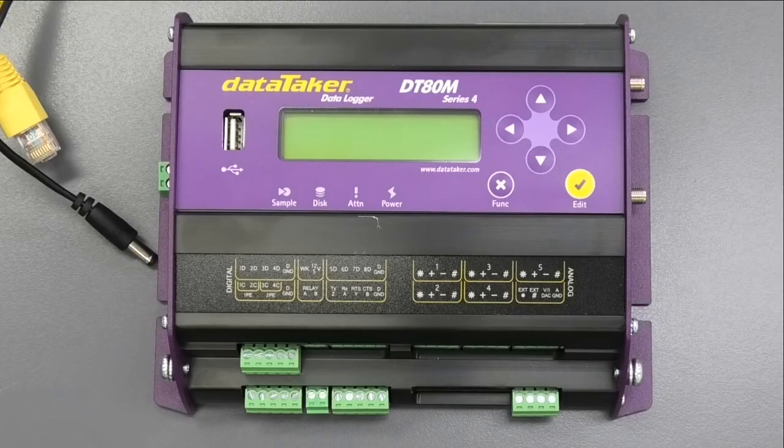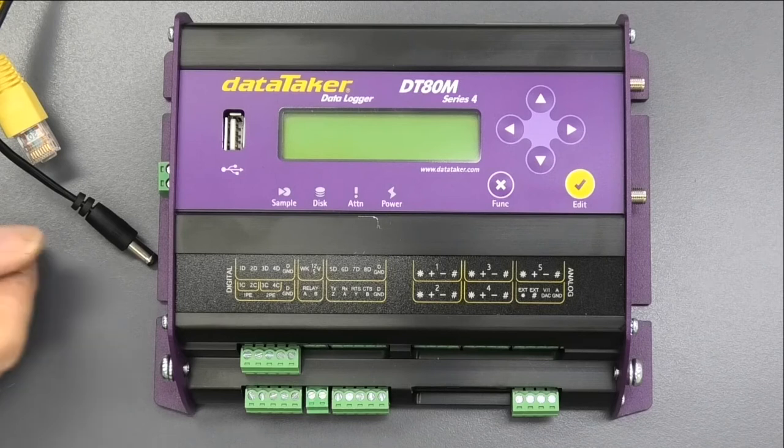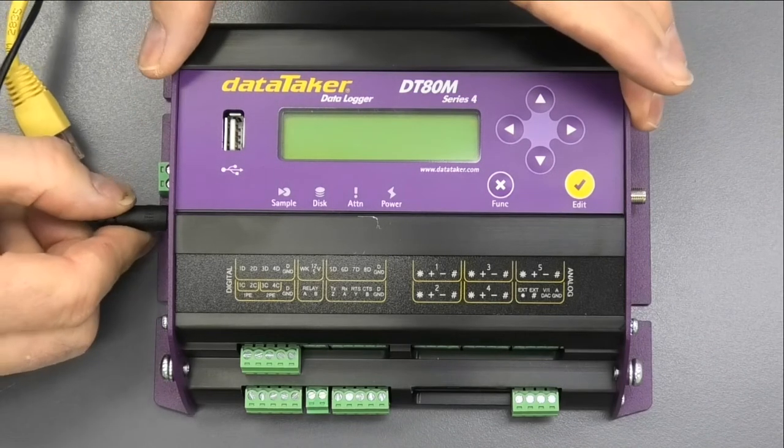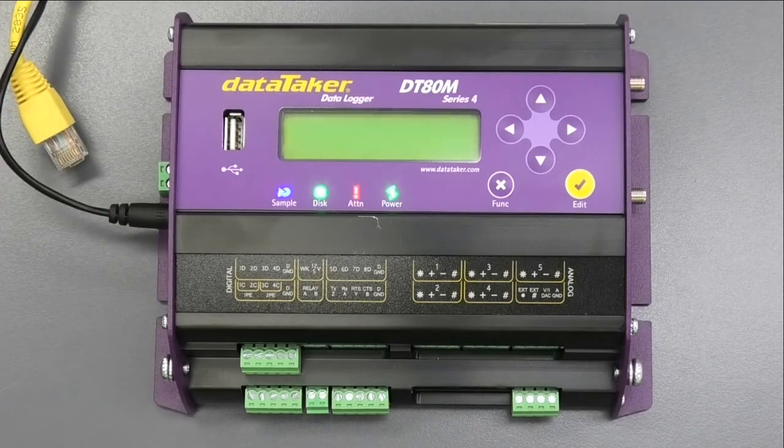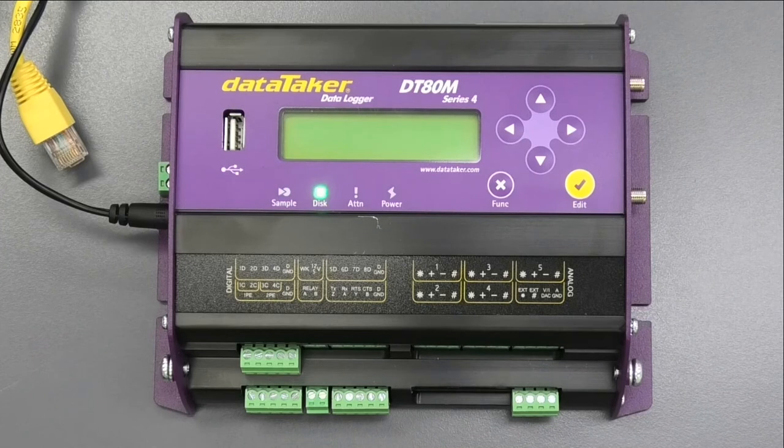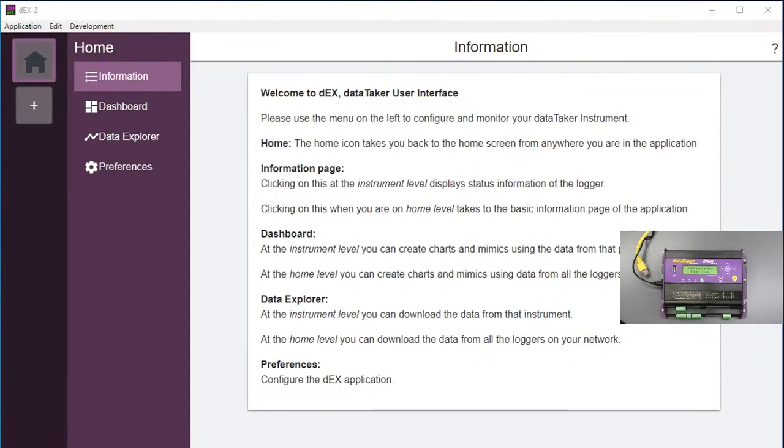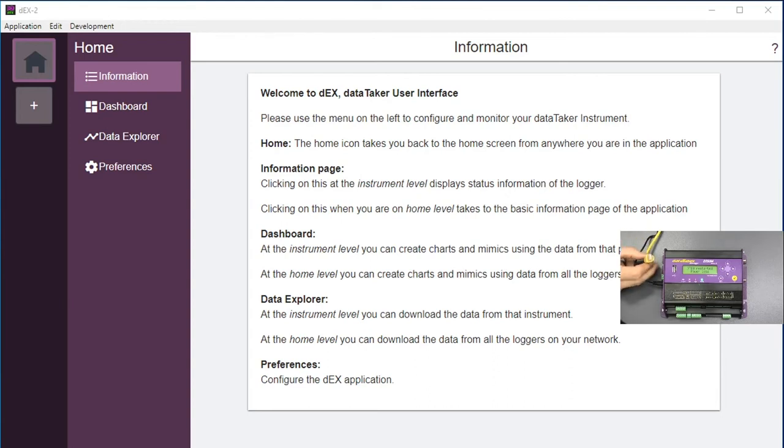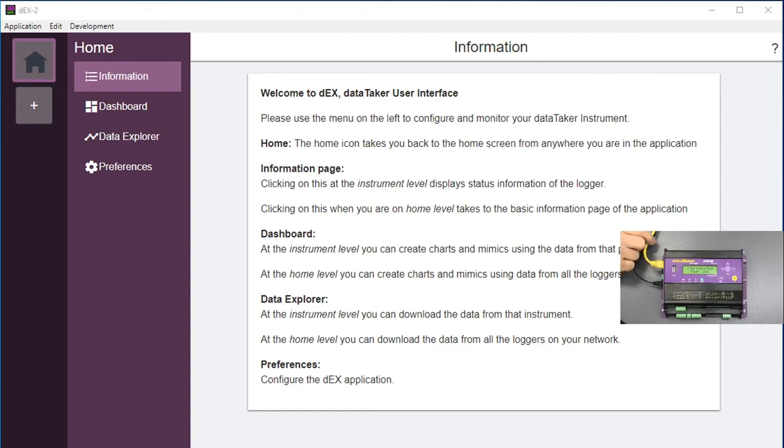These need to be configured for a specific job. So I'm just going to power the logger up. To communicate with a logger between a PC, you load this program DEX2. This is what the display screen, it comes on a memory stick. There are actually two memory sticks in the kit. We'll talk about the second in a minute. The simplest way to communicate with it is using Ethernet.